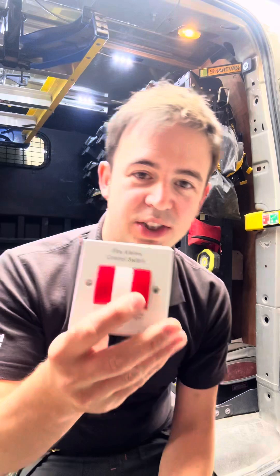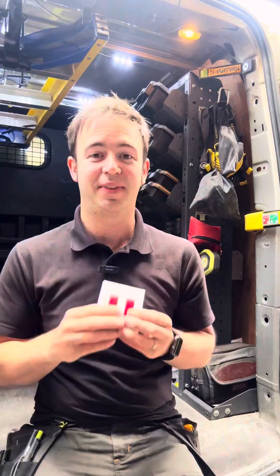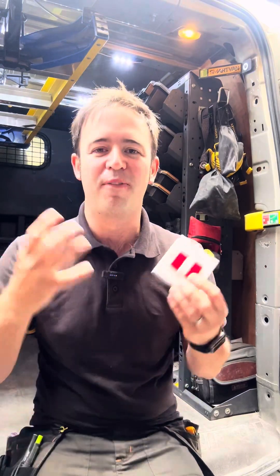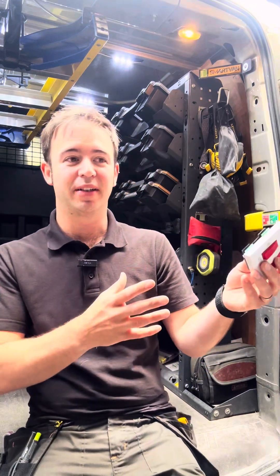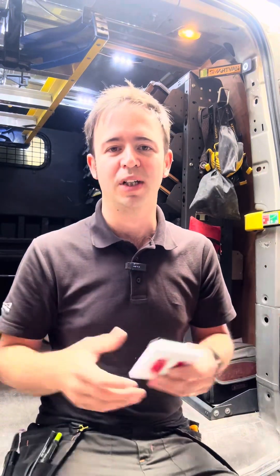It's also got the silence alarm function. When an alarm has been triggered and you press the hush button, this switch does the same remotely. I think it's about 10 minutes before the device does a little retest — if whatever initially triggered the detector is still there, it will go off again. If not, I think it does a beep and then goes back into normal operation.